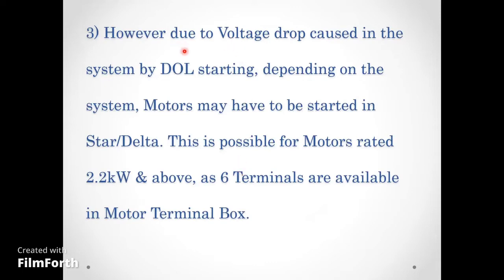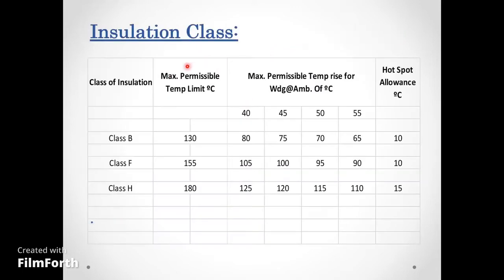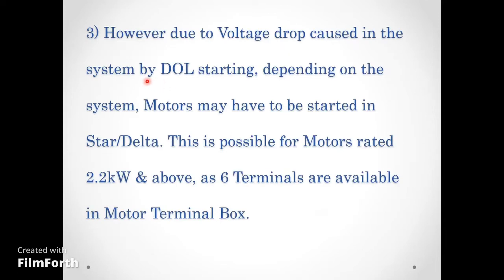However, due to voltage drop caused in the system from DOL starting, motors may need to be started in star-delta. This is possible for motors rated 2.2kW and above, since six terminals are available.